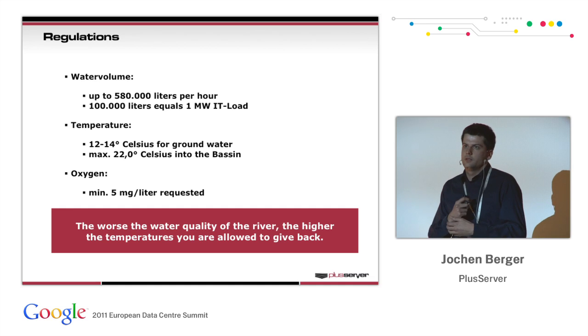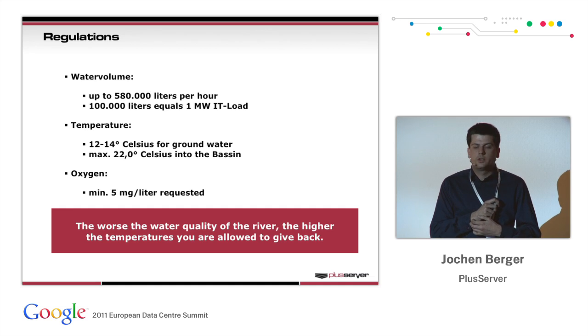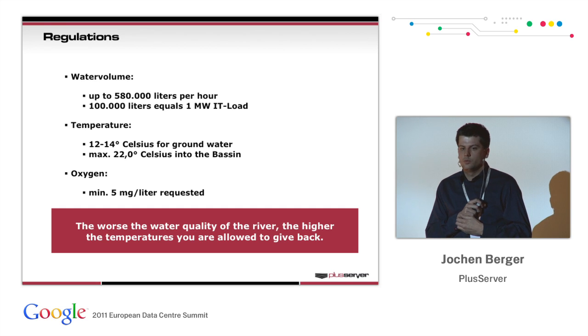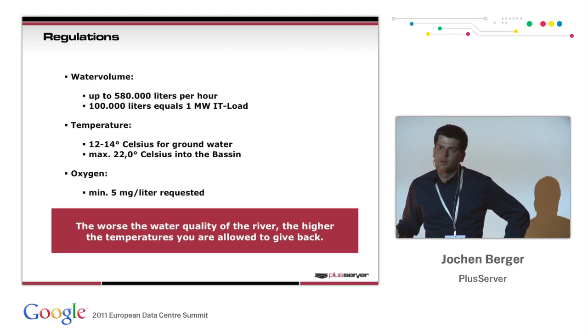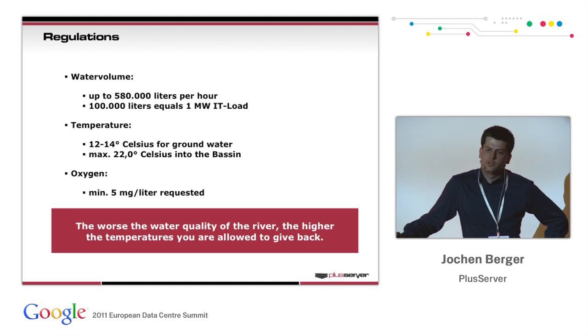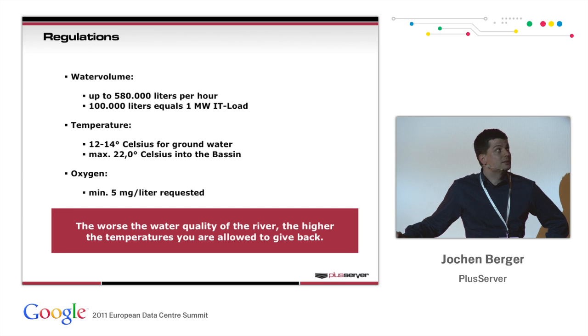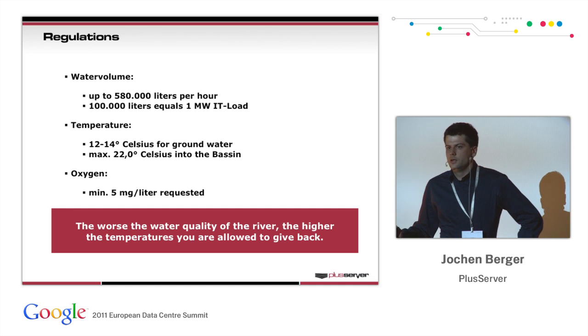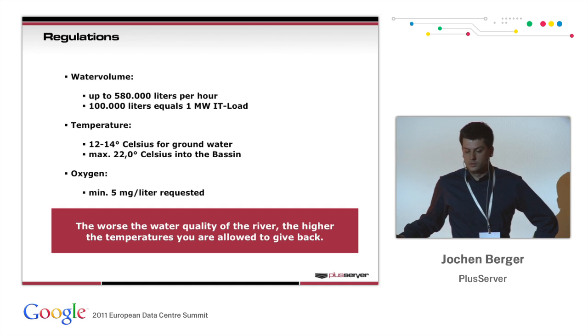Some regulations we had to keep in mind. When we started the project and when we saw that water cooling is the right way for us, together with the economic department of this area, we talked to all the regulating authorities. What they told us is that we are able to take around 580,000 liters of water per hour. And in our calculations, we saw that this 100,000 liters equals around 1 megawatt of IT load.